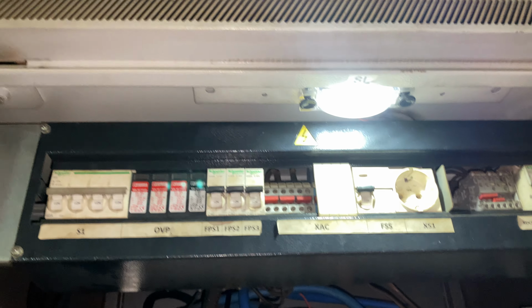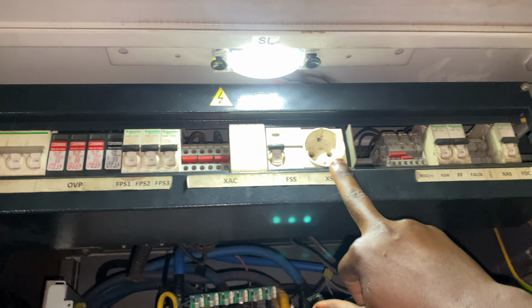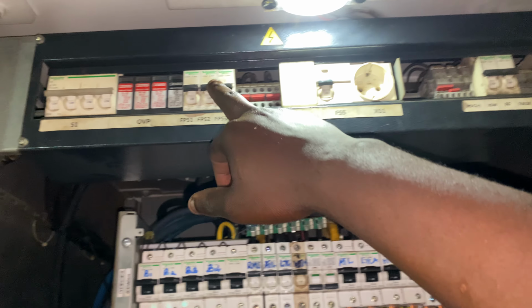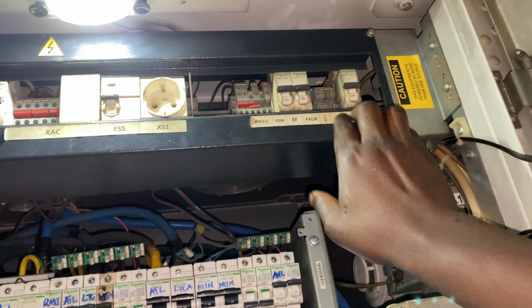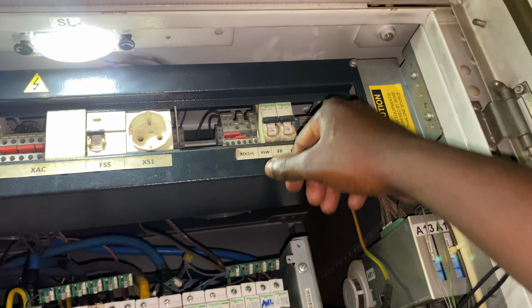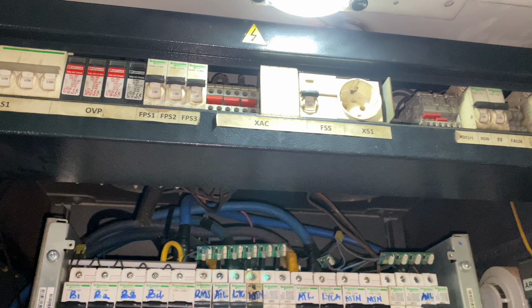But before being connected to the rectifier module, they always pick a phase here and give it to these external sockets, as you see, XS1, which is an external socket. And they also pick another phase and give it to other external sockets. So here you can put other things, external sockets, fans. This socket, which is for AC, we always use to connect other AC equipment like that blower, in case we want to blow some dust away. That's why we have a provision of that external socket.